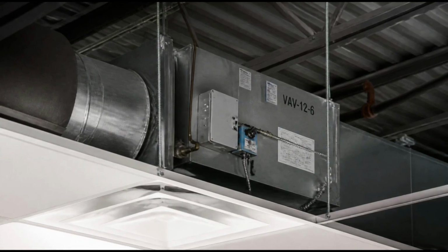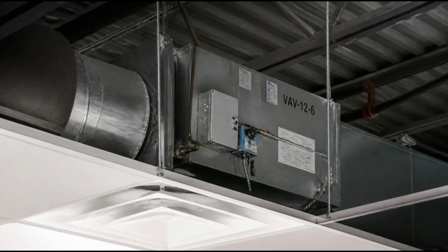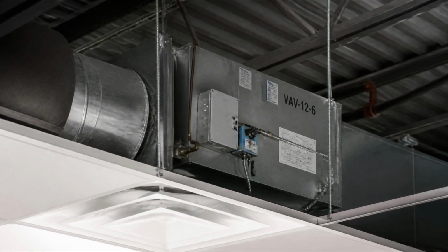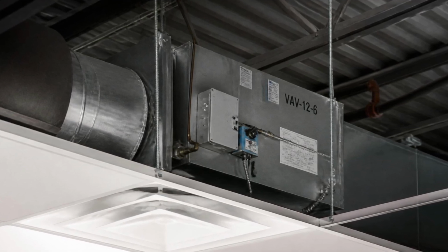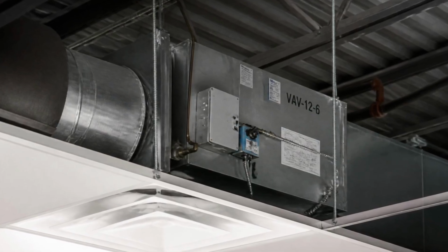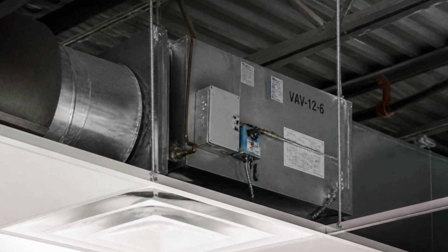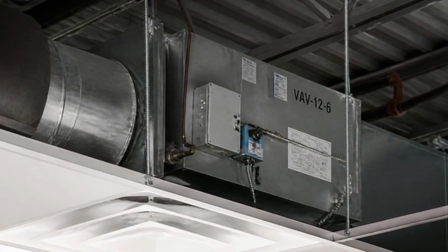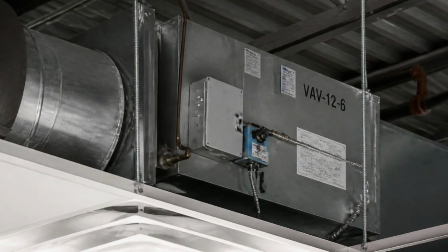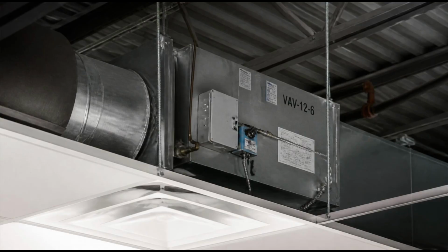The system finds a balance. Some return air may be mixed with fresh outside air. That mixing happens at the air handler, where dampers control the proportions. Outside air dampers and return air dampers work together, opening and closing in coordinated ways to achieve the right blend. Building codes and ventilation standards often specify minimum quantities of fresh air that must be introduced per person or per square foot of occupied space. The system is designed to meet those minimums while also allowing for flexibility based on conditions.